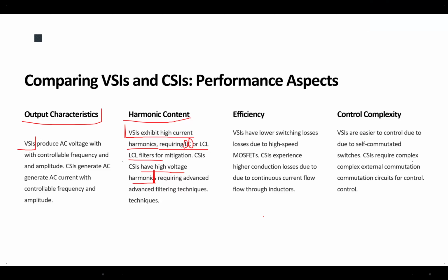So that process, because it uses Ohm's law, basically means the filter itself does not work on a voltage. It works to reduce the harmonics on a current. Voltage is an input, it uses Ohm's law, so the output is current.